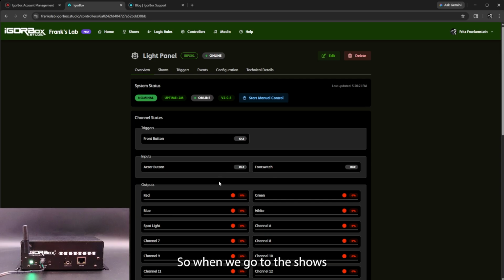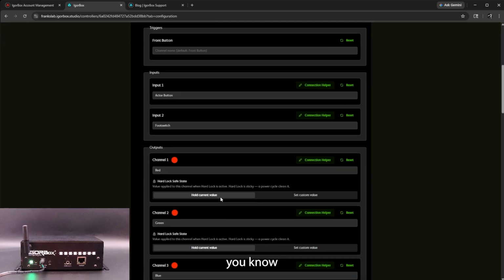So when we go to the shows in a later video, you'll see that these channel names will propagate to the shows, they'll propagate to your logic rules, they'll allow you to name them. You're going to name it on the controller, right? The thinking being that you're wiring the controller, you know what's on that channel, you should set what's on that channel for that controller, and then that propagates through everything else.